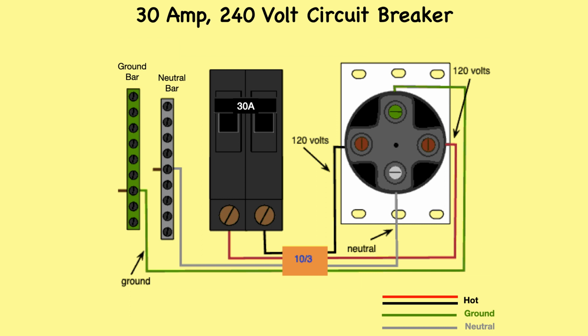This illustrates a new 30 amp circuit breaker feeding a 30 amp dryer outlet. This is an upgrade of the outdated 30 amp circuit in the previous diagram. This breaker is connected to a 30 amp receptacle, with 10-3 cable, and a ground wire is included for protection against electrocution not provided by the older circuit.